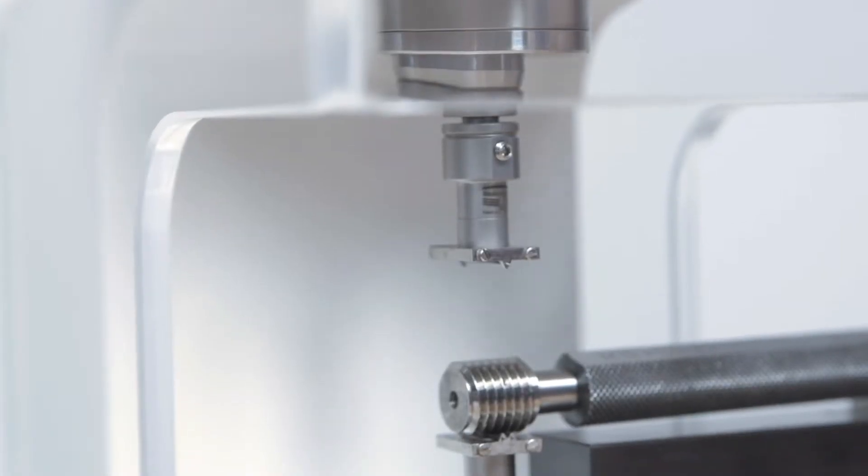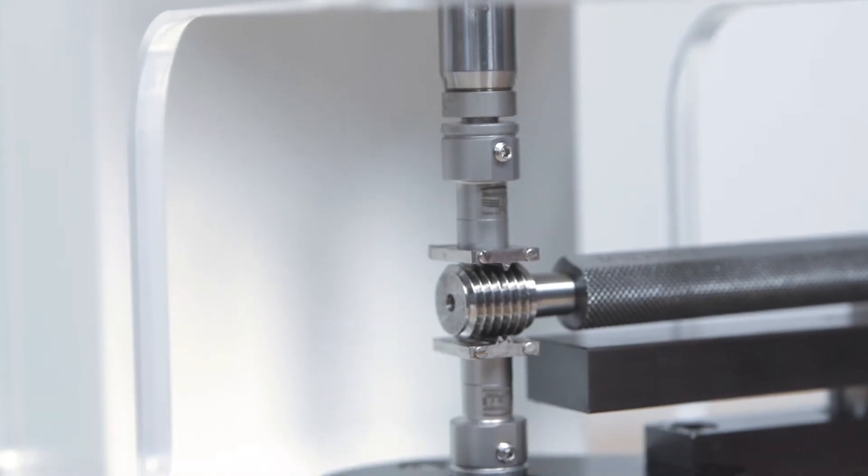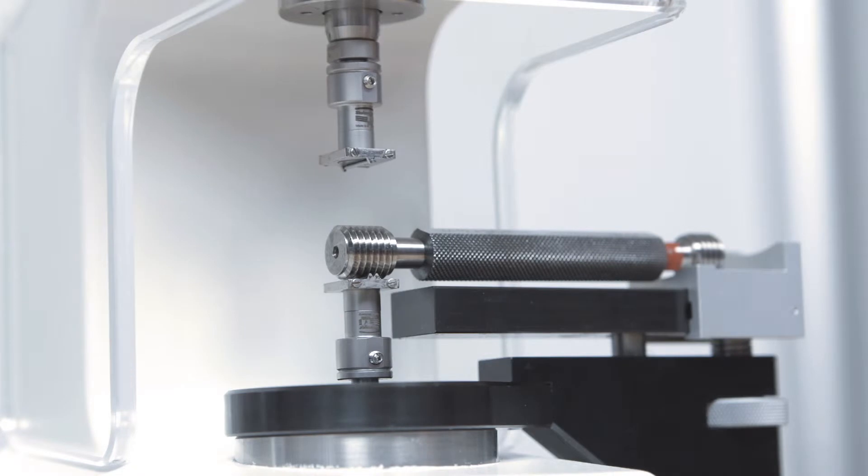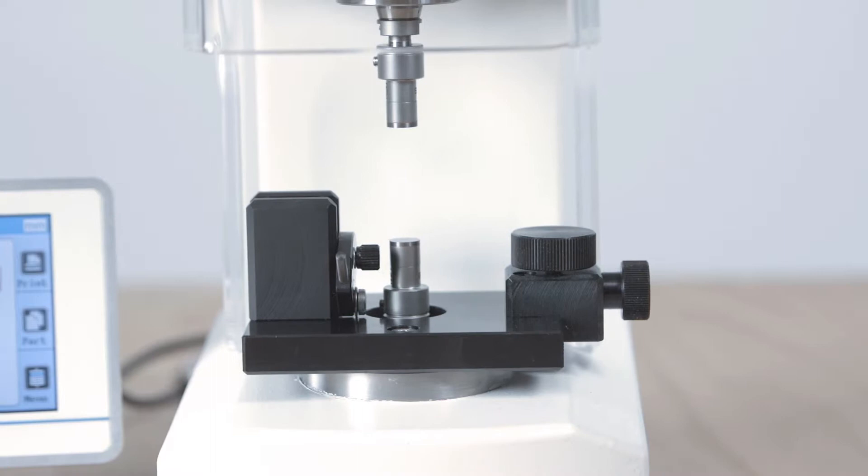Thread plug gauges up to M28 can also be tested using the setup. To this end, measuring wires that are guided in a metal frame are placed on the flat 8 mm measuring surfaces.